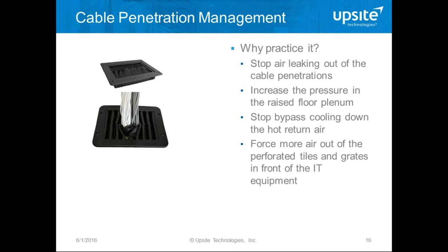Why should we install cable penetration management? We want to stop the cold air leaking and put it in front of the IT equipment. This increases pressure in the raised floor and will improve flow distribution through the tiles. It will reduce bypass and force more cold air out of the grilles and perforated tiles.